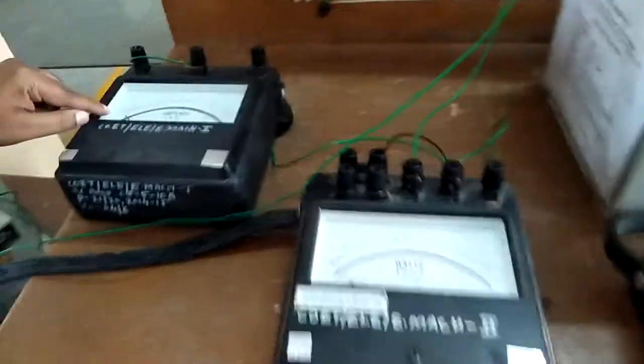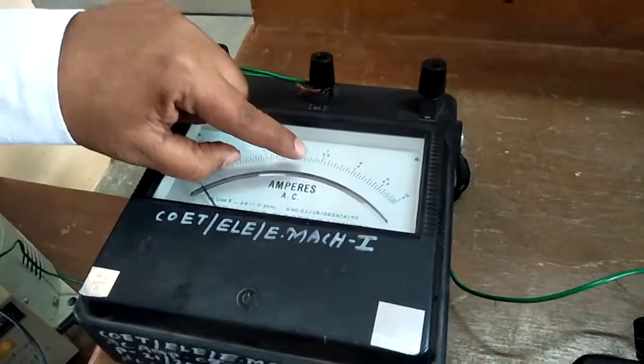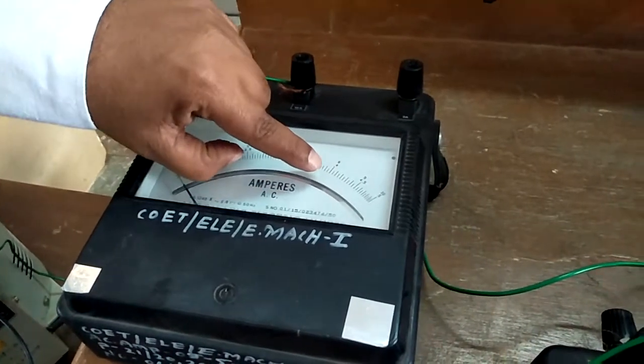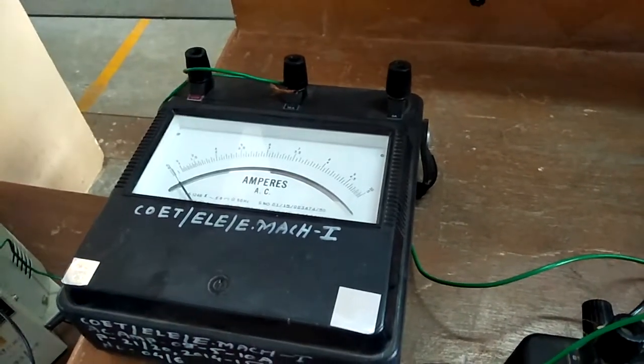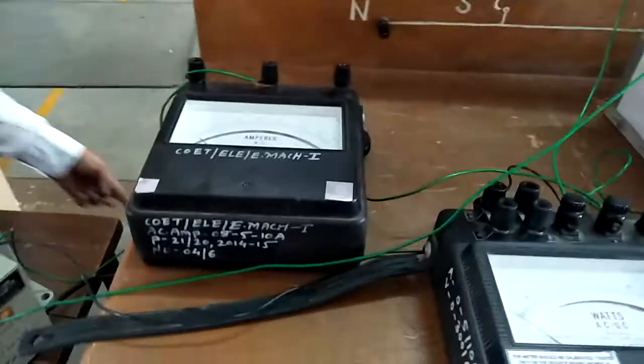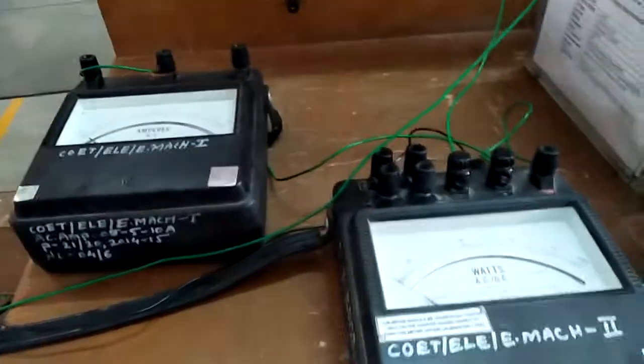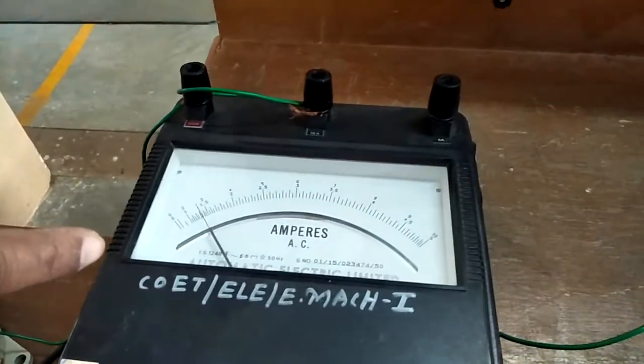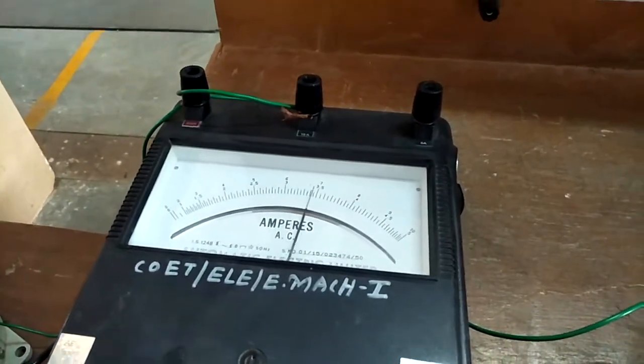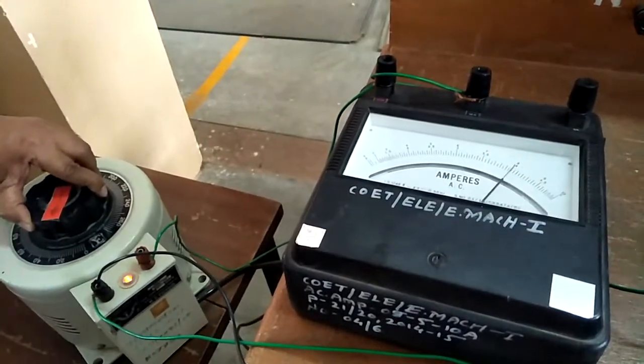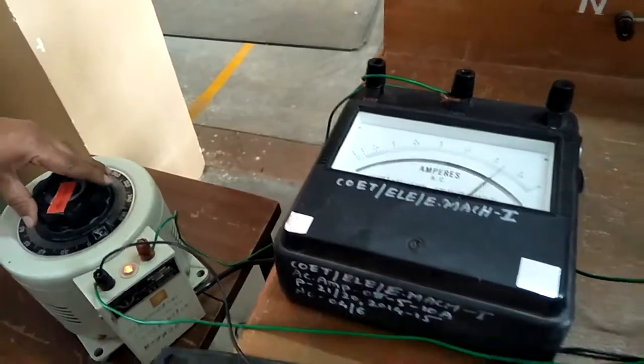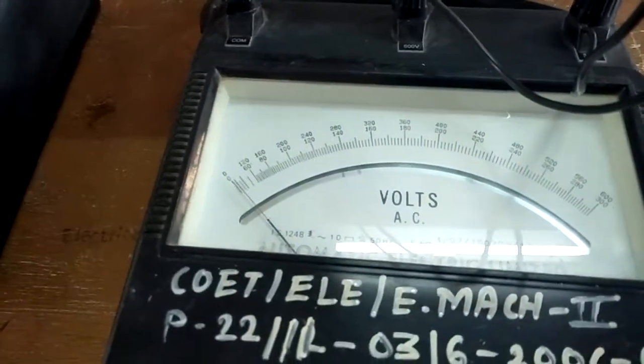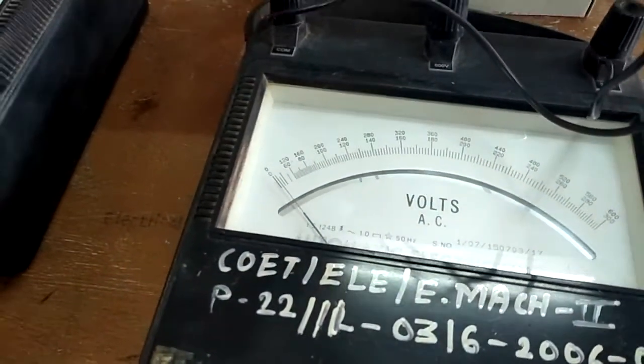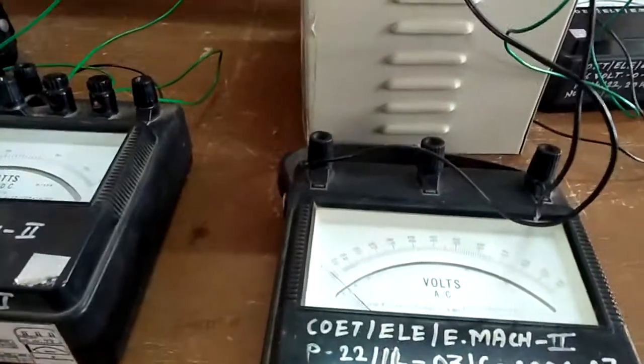Okay, so as soon as the current reaches 8.6 ampere, we have to take the reading very quickly and very carefully. Now see here, as soon as we increase the small voltage, the current increases drastically, isn't it? Even at a small voltage of 11 or 13 volt, it is going to circulate 8.6 ampere, and this is going to measure the power under the short circuit condition, and the voltage is very small, it is 11 volt. So we will quickly switch off the supply because our transformer is short circuited.